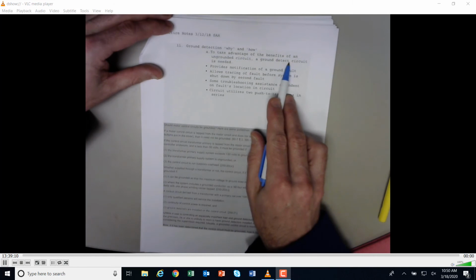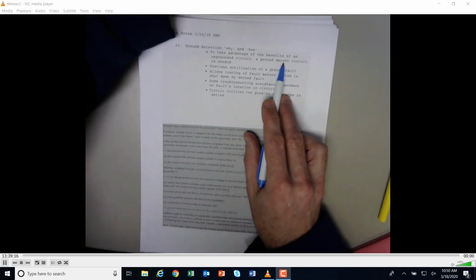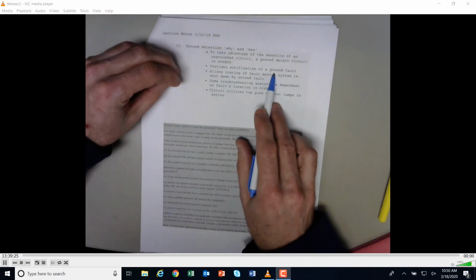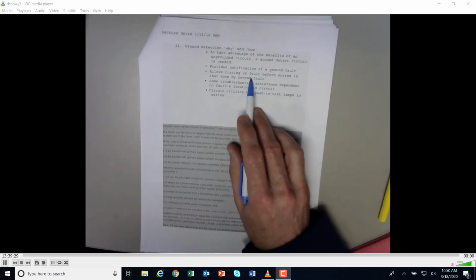To take advantage of the benefits of an ungrounded circuit, a ground detect circuit is needed. And that's, once again, where you can leave the circuit energized and troubleshoot it a little bit. You've got to be careful, though. You don't want to electrocute yourself. You must provide notification of the ground fault. So that's why we have the ground fault light. It allows tracing the fault before the system is shut down by the second fault.